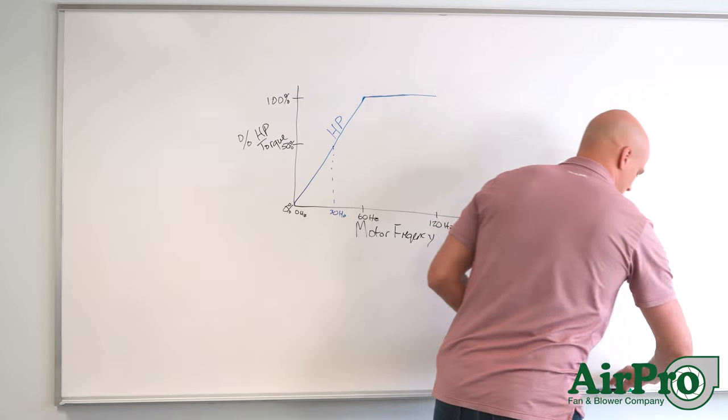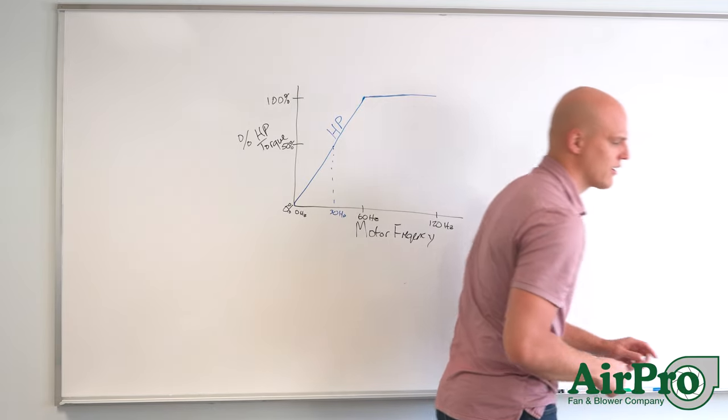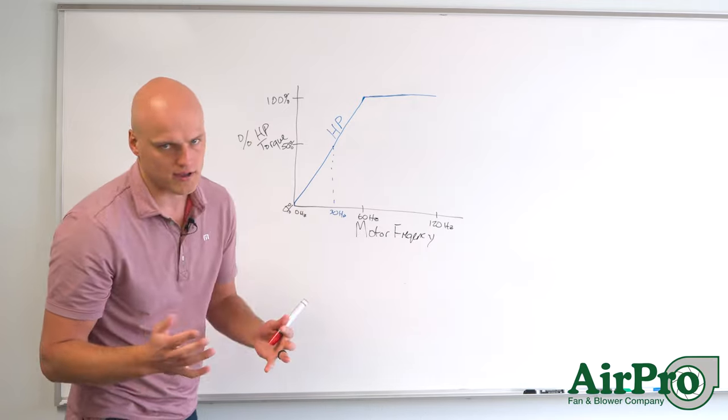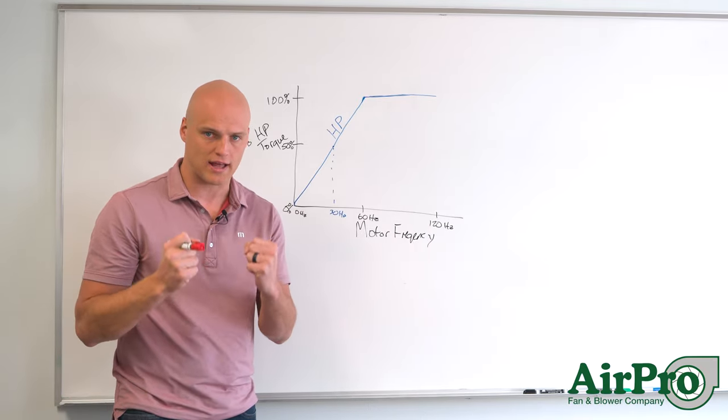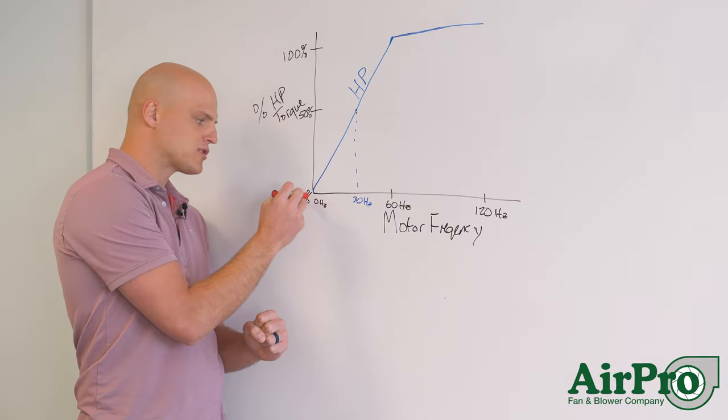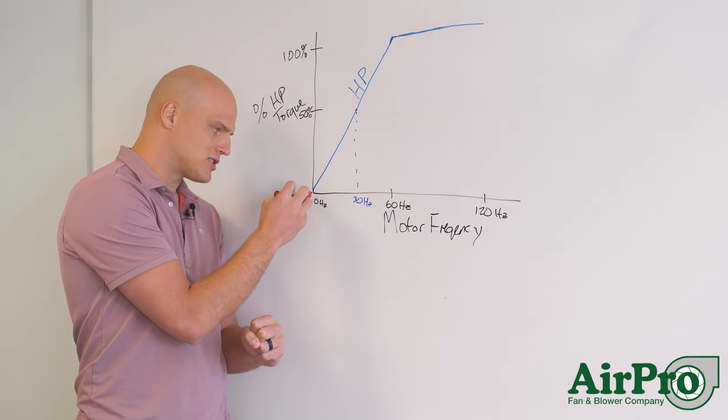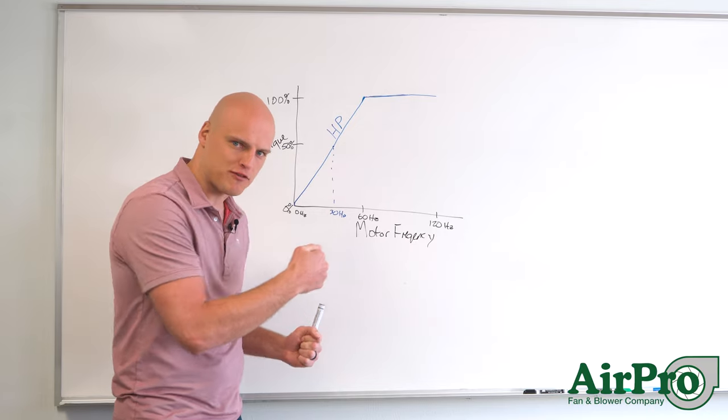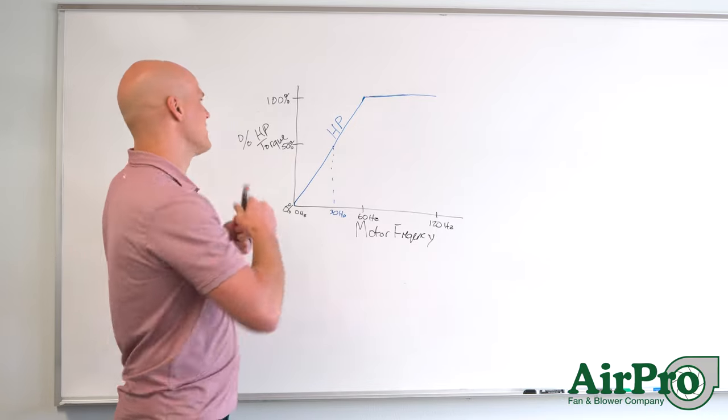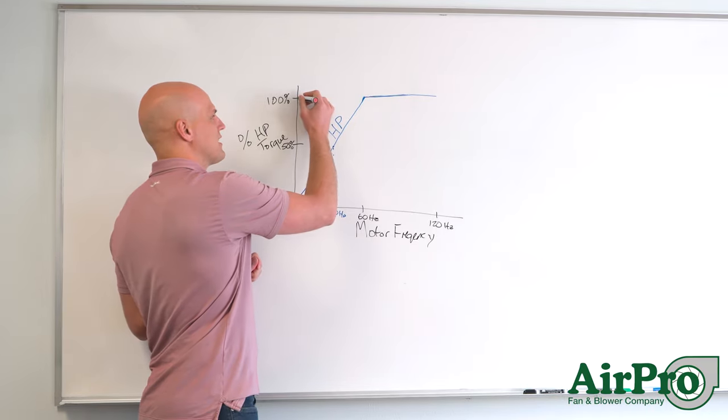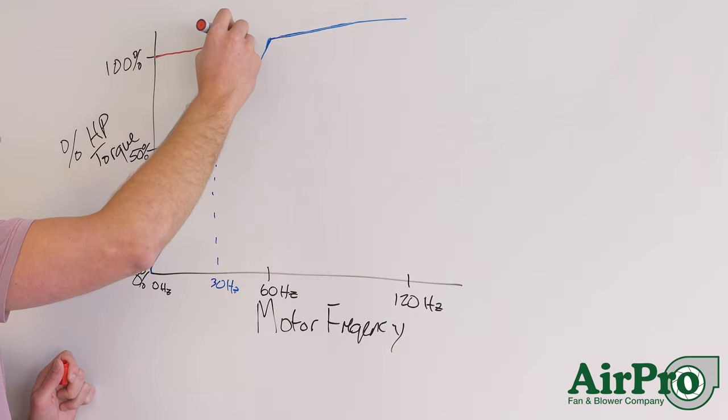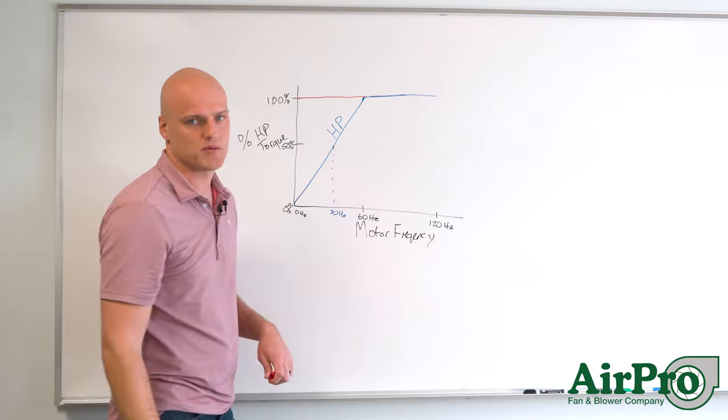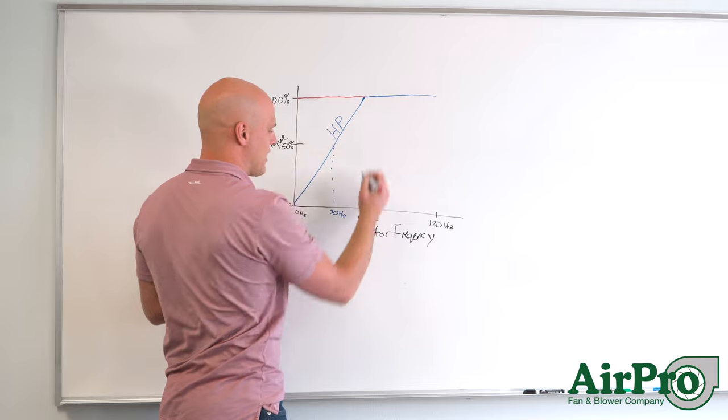Okay the second curve we're going to write on here is the torque available. Again what we care about with industrial fans is the torque at startup. So we want the most torque we can when this thing is just past zero hertz and you're firing it up. Good news your torque starts at a hundred percent. So again from zero hertz to 60 hertz we have a hundred percent of the available torque from the motor all the way out here to 60 hertz.